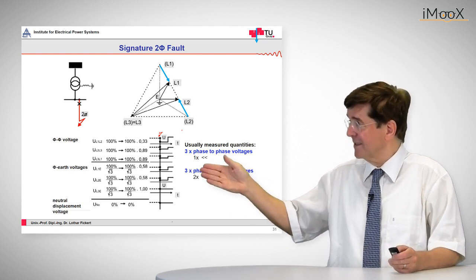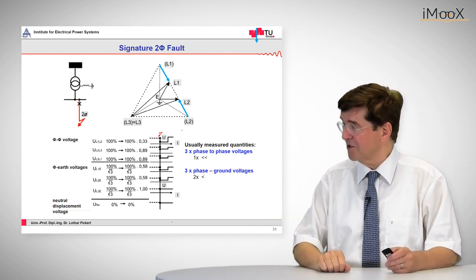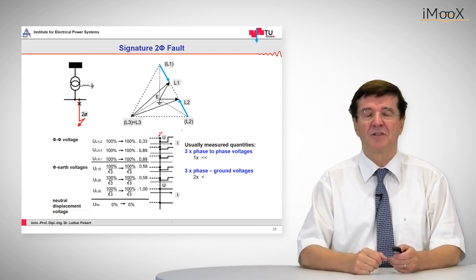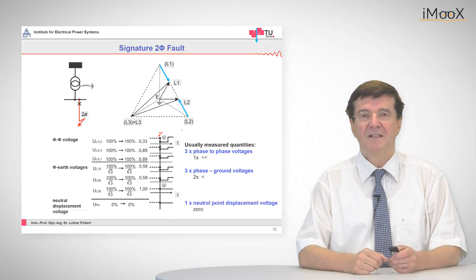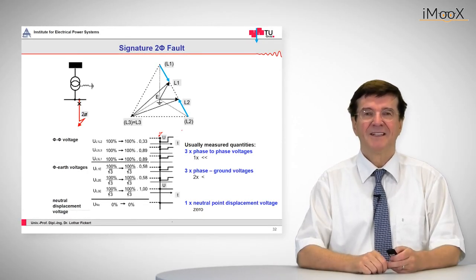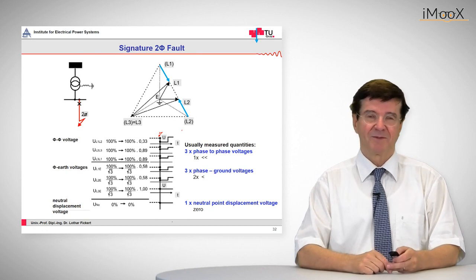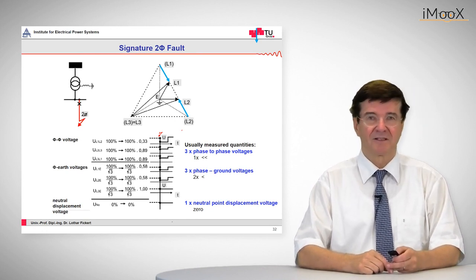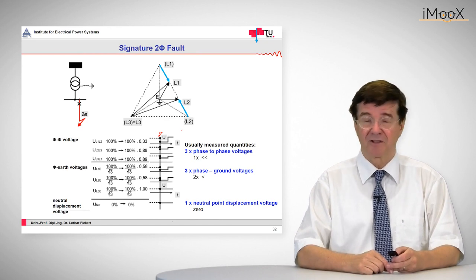The next set of traces are the phase-to-ground voltages. Here we can see that two of these phase-to-ground voltages are afflicted and this is important in this kind of failure. There is no neutral displacement voltage because, as can be shown, zero sequence current and zero sequence voltages are not involved.